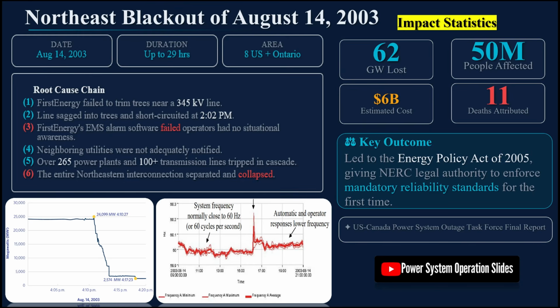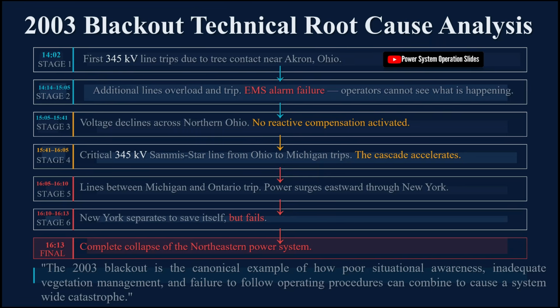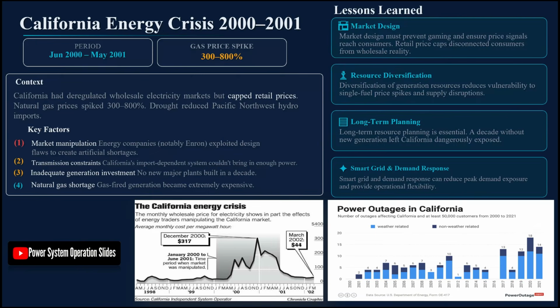If the grid does collapse, the restoration process begins with black start units, typically hydro or gas turbines that can restart without external power to re-energize the system. Operators must then carefully synchronize islands and pick up load in small increments while managing voltage and frequency control in a weakened, soft grid environment.